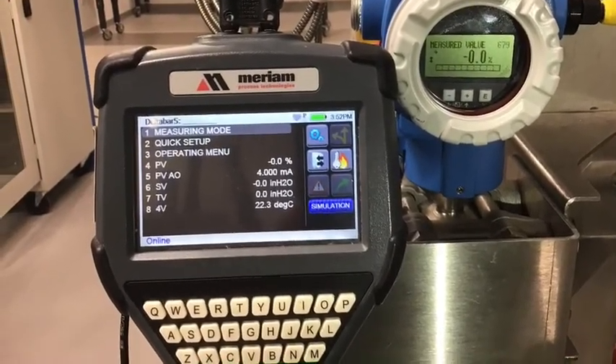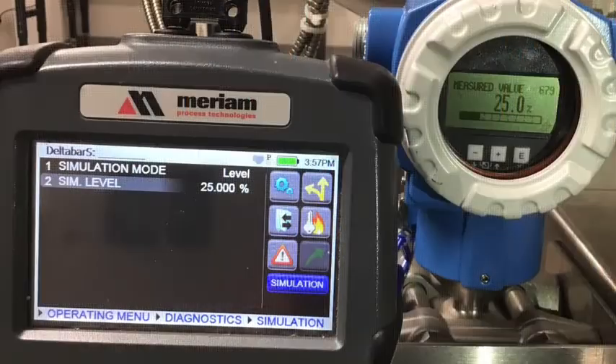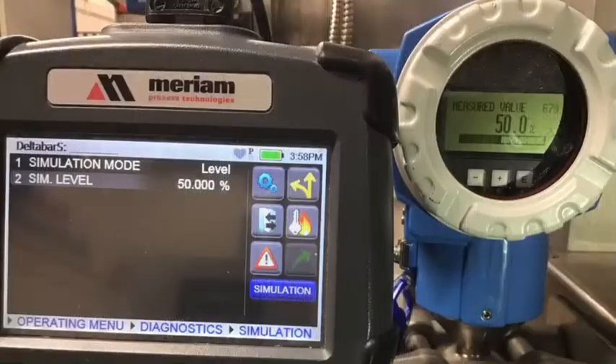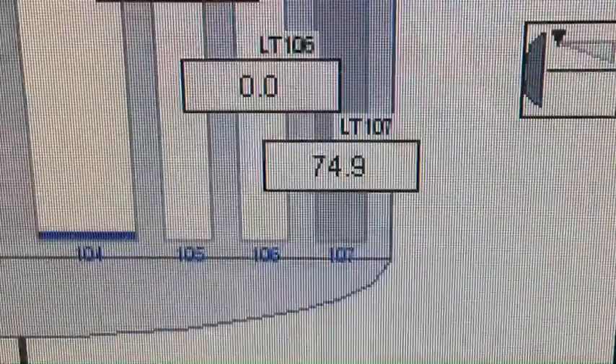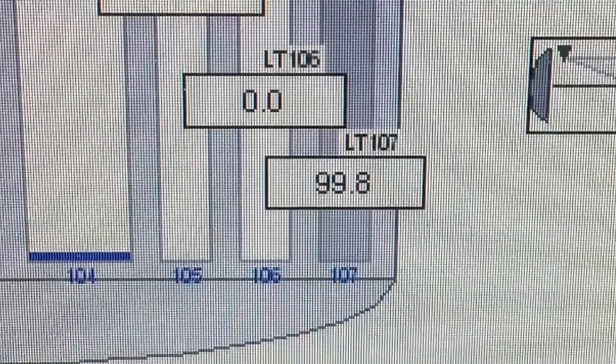Verify the correct reading on the PLC screen. The Meriam can be placed into a simulation mode and command the transmitter to output various levels — normally 0, 25, 50, 75, and 100% of the transmitter output is used. This method of loop confirmation is performed throughout the process industry.